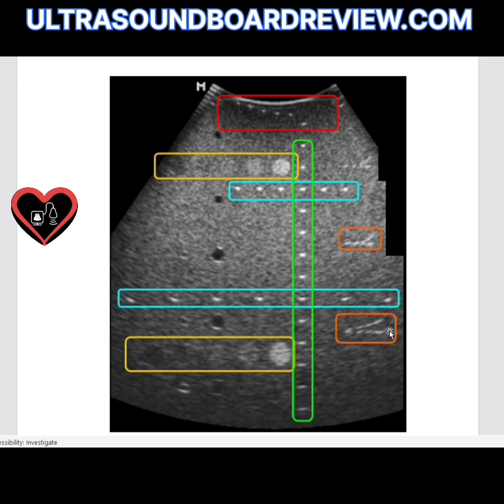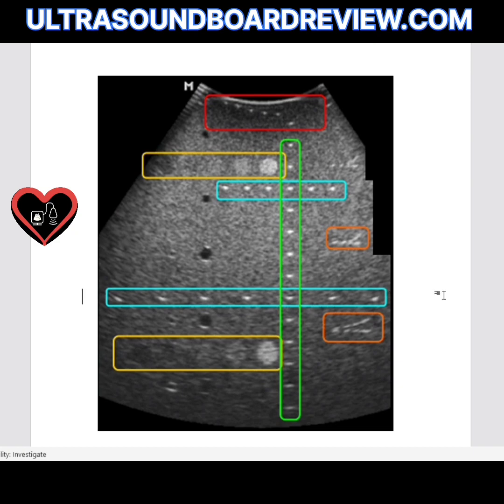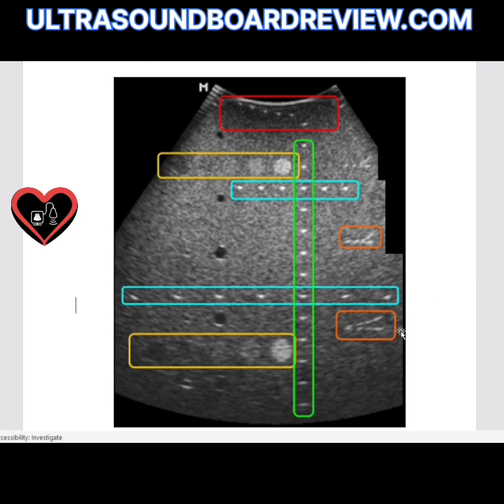You can see the space between dots here, here, and here because the SPL is shorter than the distance between these two dots. If the beam is coming from the side, then it's evaluating lateral resolution. This determines the ability to accurately identify two reflectors perpendicular to the sound beam. When the beam comes from the top, it determines the ability to accurately identify two reflectors parallel to the ultrasound beam.